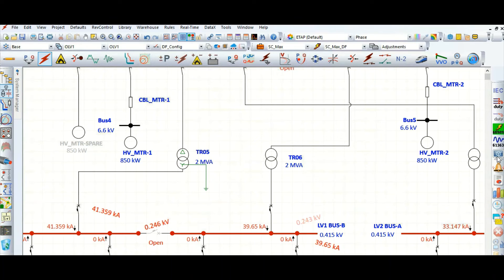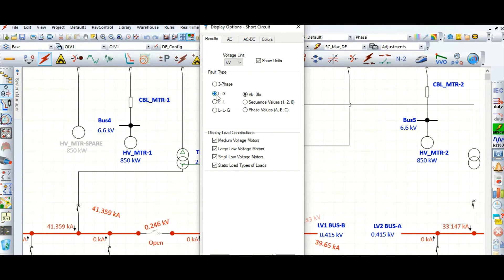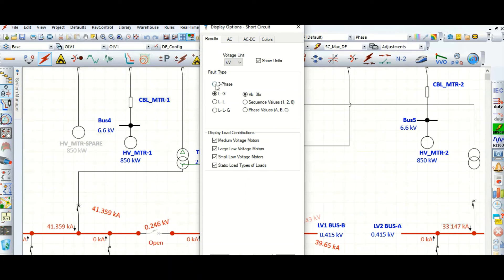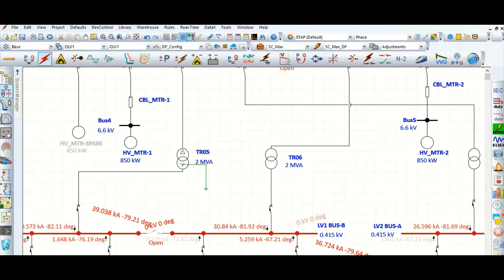Go to the display option. With single line to ground fault selected, the result is 41.359 kilo amperes. Because we have not limited the neutral grounding current, it is coming as 41.359 kA. If we check three-phase, it is 39.038 kilo amperes.